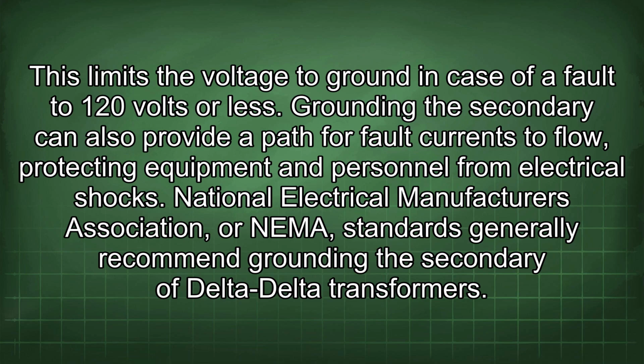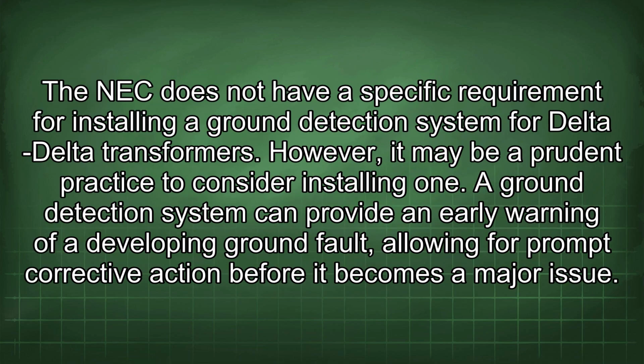National Electrical Manufacturers Association, or NEMA, standards generally recommend grounding the secondary of delta-delta transformers. The NEC does not have a specific requirement for installing a ground detection system for delta-delta transformers. However, it may be a prudent practice to consider installing one. A ground detection system can provide an early warning of a developing ground fault, allowing for prompt corrective action before it becomes a major issue.